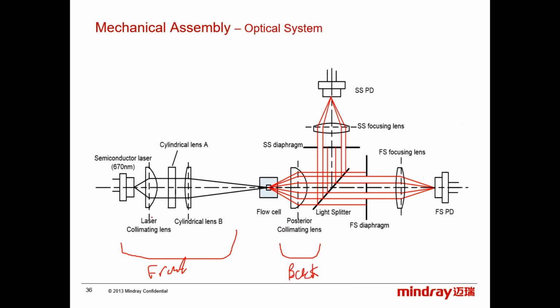So what do we have here? We have the laser collimated lenses. You see, it will collimate my signal. This is cylindrical lens A, cylindrical lens B, and here we focus the signal on the flow cell. So here we converge it, and here we diverge the signal using the posterior collimated lenses. This is the light splitter, and then we focus the laser again on the photodiode. The same thing here: we focus before we enter the SS detector.